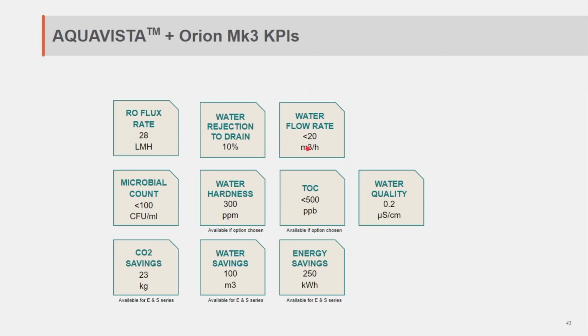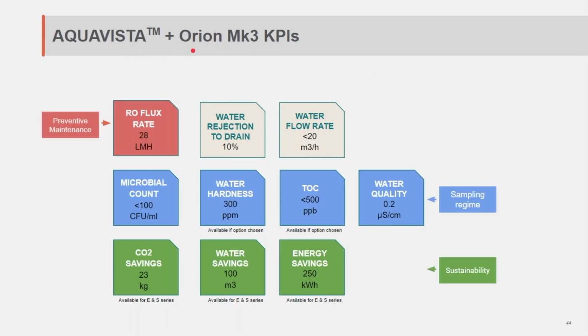And if we take, for example, an Orion unit, these are some of the KPIs that can be set up, things like the RO flux rate for preventative maintenance. So if the flux rate reaches a certain alarm point, a warning comes up saying that it would be a good idea to organize a chemical clean on the RO before it fails. So again, it's just like the maintenance light in your car. When that comes on, it says you may have 1,000 kilometers left before you need to do your service. You can book that in before those 1,000 kilometers get down to zero. So it's the same sort of principle.